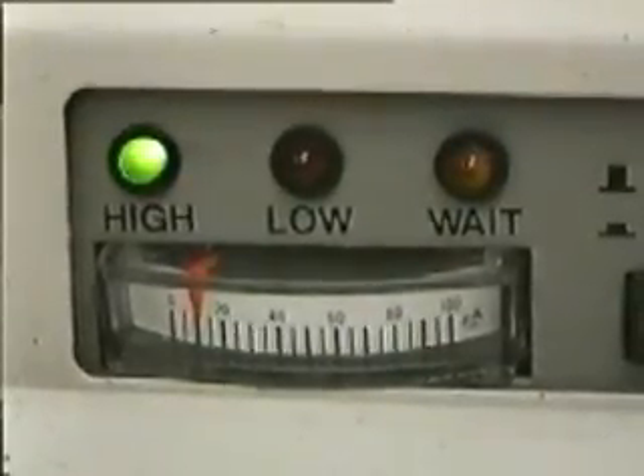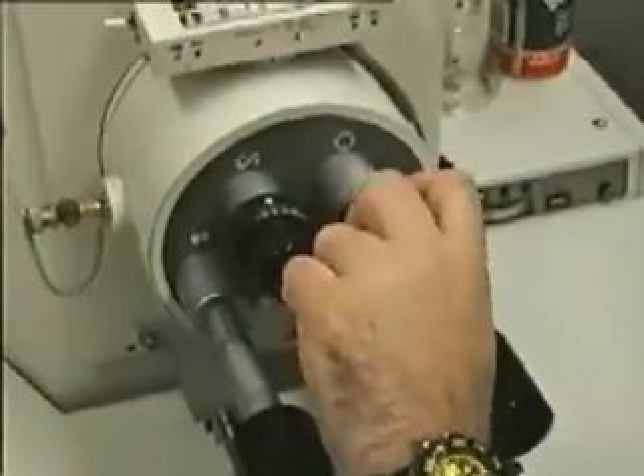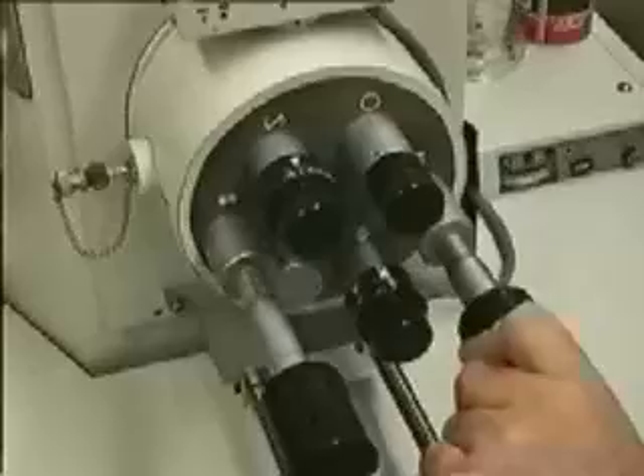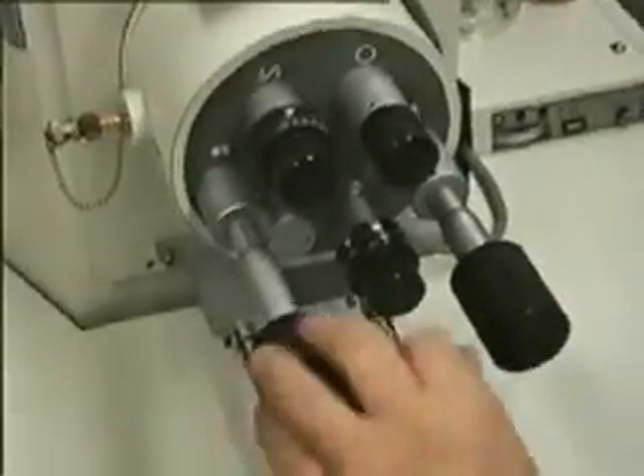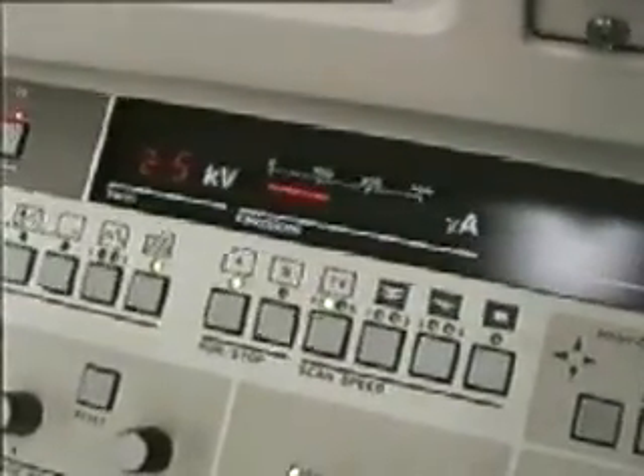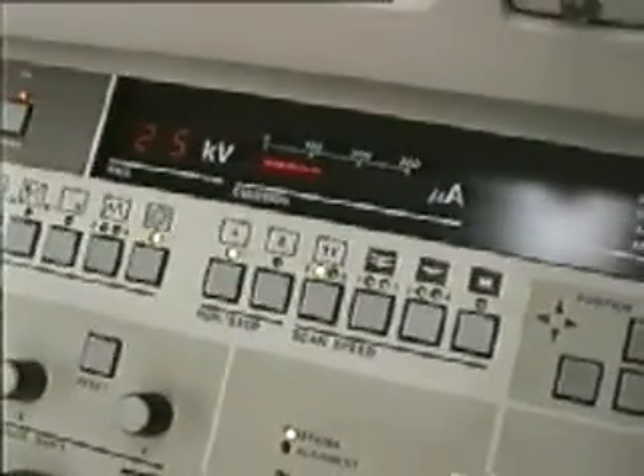microscope to be operated. First, a small video camera inside the specimen chamber shows the orientation of the specimen relative to the electron-optical components of the microscope. The specimen can be rotated, tilted, or laterally displaced. Using mechanical drives on the stage, the operator can position the specimen into a desired orientation. Then the operator can select an accelerating voltage, the electron beam current, to be used in observing the specimen.